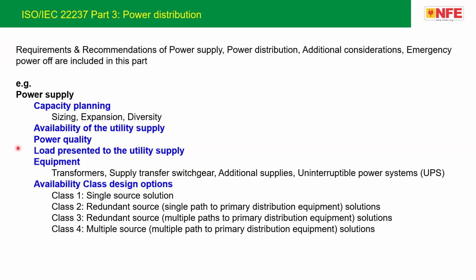For the transformer, we have to take care how the transformer is designed with respect to the peak load, including the peak design ambient temperature, where it is located, and how the load is fed from that transformer, including the UPS and drive also. It will be outside of the building, and the housing should be such that there is no risk of fire. So the design has to take care as per IEC for the oil type or dry type transformer that we are going to use.